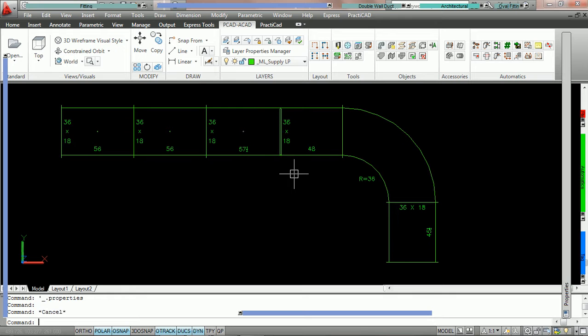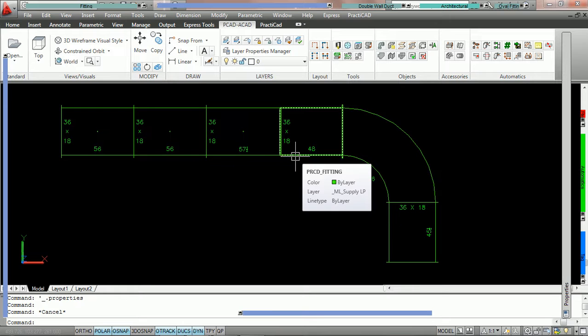So what we have now is a connector in the middle of this duct line that is actually not what the 2-inch water gauge spec table calls for. We've changed it to slip and drive, but PractiCAD, the spec that it was under, says it should be TDF.